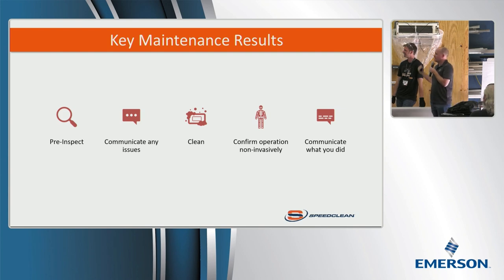So key things we need to do on a maintenance: we need to pre-inspect first. If you're showing up and immediately starting your cleaning, stop doing that. You want to make sure you pre-inspect first. This is important because if anything is not working on the equipment, it's your fault if you started cleaning and it was working before you showed up. So check everything else out. You get a scope of what you're about to do, but also you confirm, is there actually a problem?